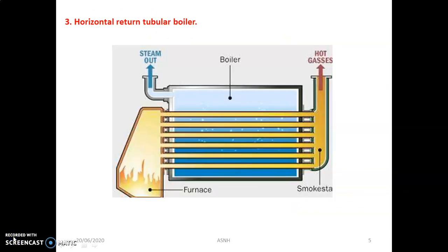The third important fire tube boiler is the horizontal return tubular boiler. The arrangement of the tubes and the boiler shell is horizontal, hence the name. The furnace, or combustion chamber, is on the left corner where combustion of fuel is carried out, and the tremendous amount of fumes generated continuously pass through the tube bundle. The flue gases flow through the tubes, exit through the draught system, and enter the atmosphere through the chimney. The rest of the shell is covered by water.